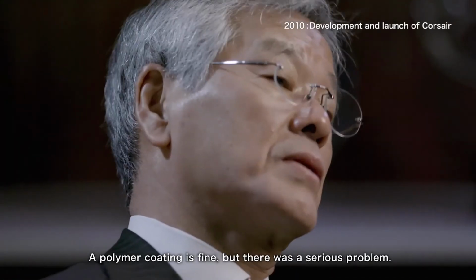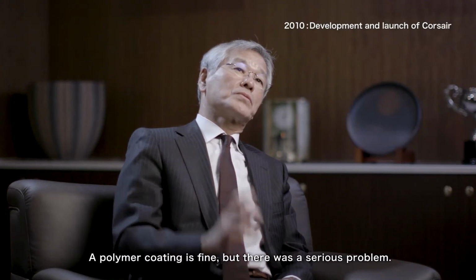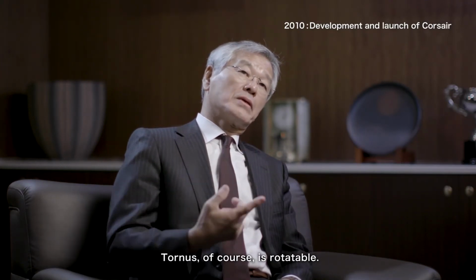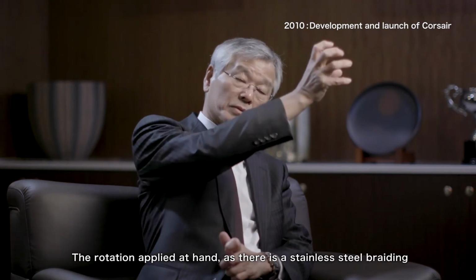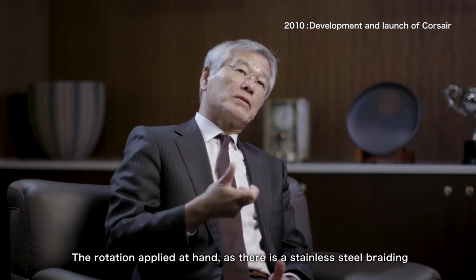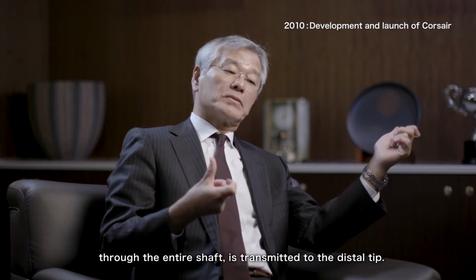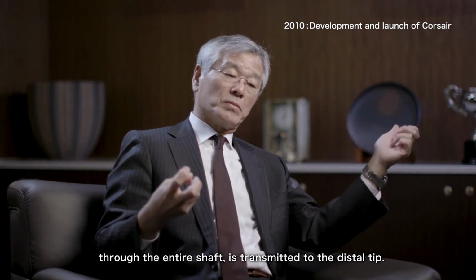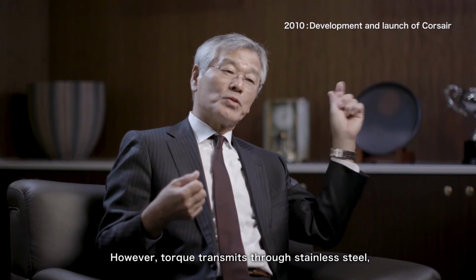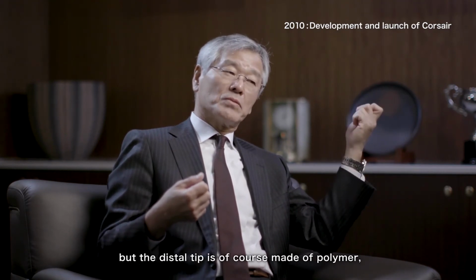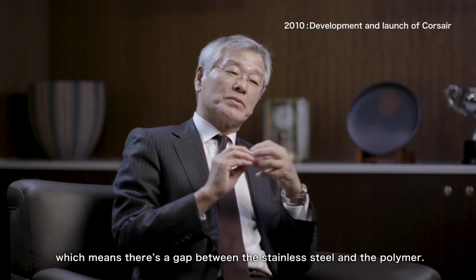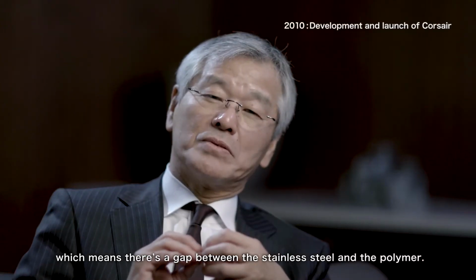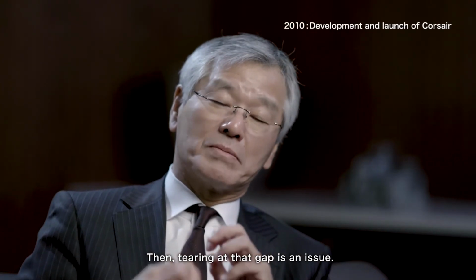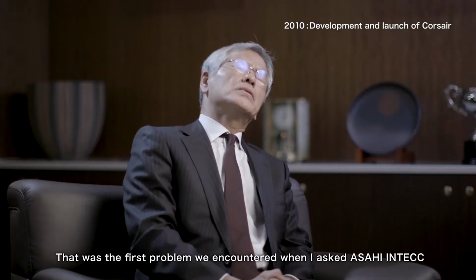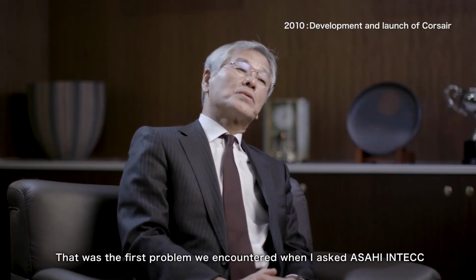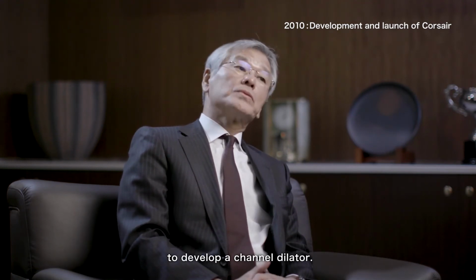A polymer coating is fine, but there was a serious problem. Corsair, of course, is rotatable. The rotation applied at hand, as there is a stainless steel braiding through the entire shaft, is transmitted to the distal tip. However, torque transmits through stainless steel, but the distal tip is of course made of polymer, which means there's a gap between the stainless steel and the polymer. Then tearing at that gap is an issue. That was the first problem we encountered when I asked Asahi Intech to develop a channel dilator.